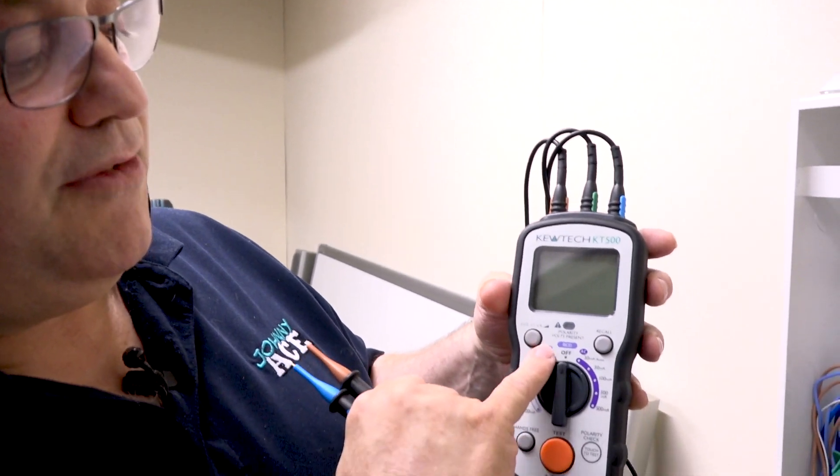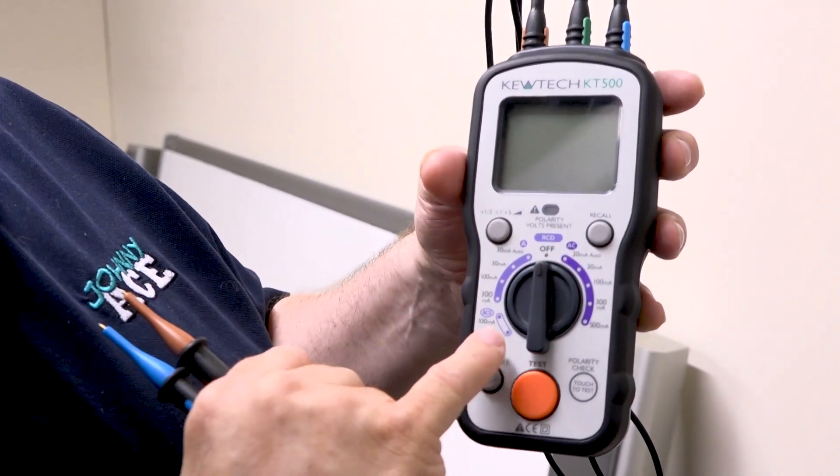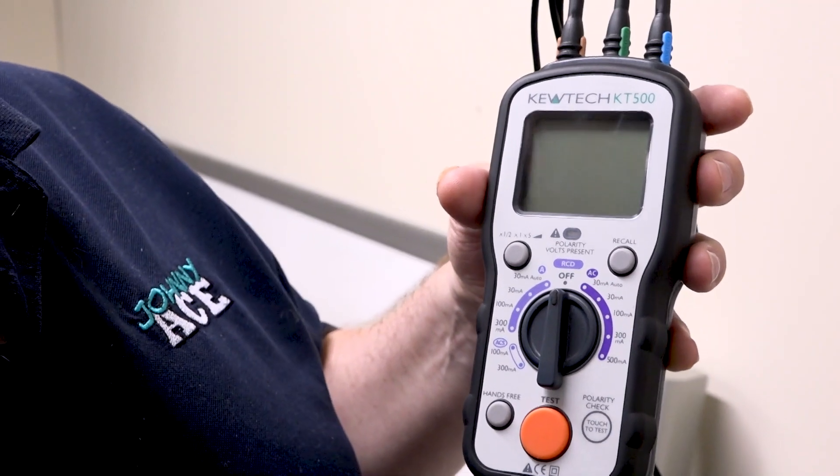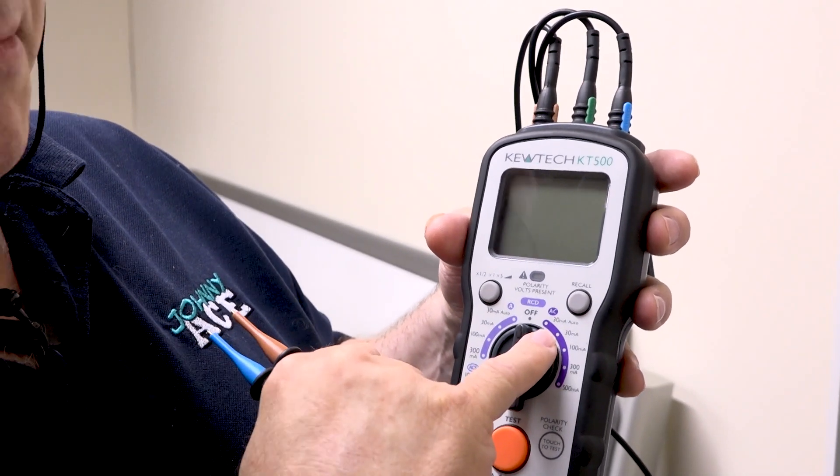So we're running a short demonstration testing an RCBO unit in this board here. It's a Type AC unit, and if you look at the tester you'll see you've got Type A, Type AC, and Type S. So we'll be using the Type AC side there, and we're going to be doing it in the auto mode because it's a 30 milliamp. Okay, so let's have a go.